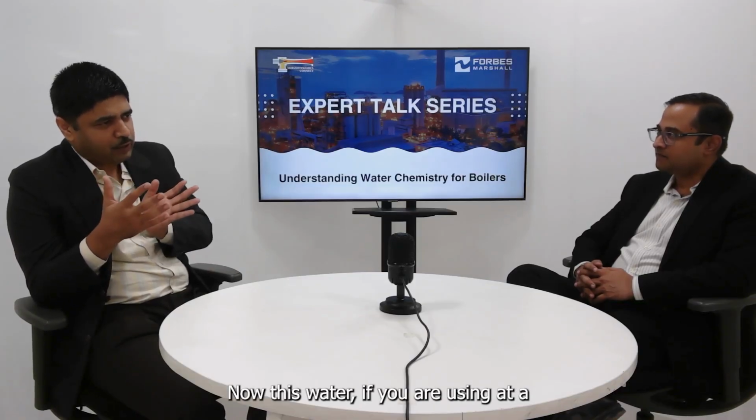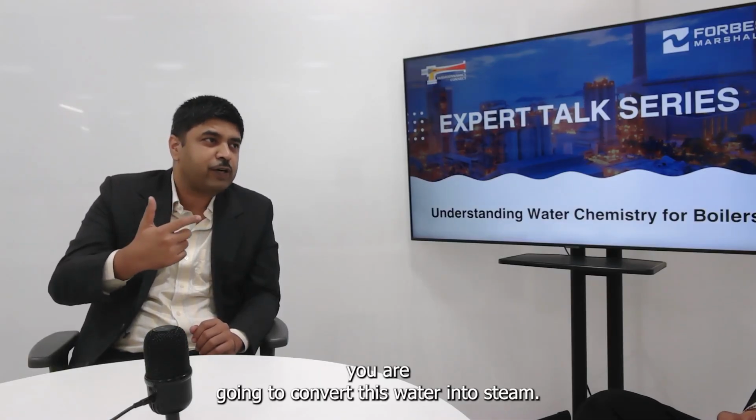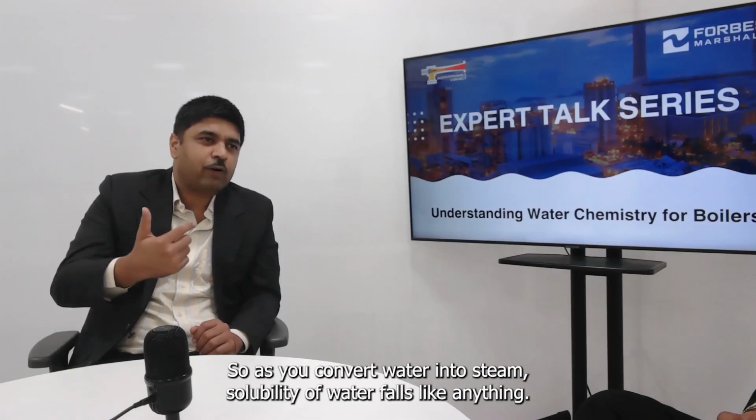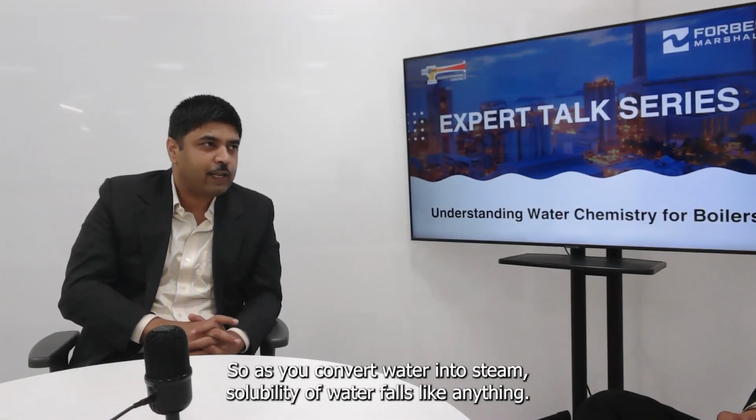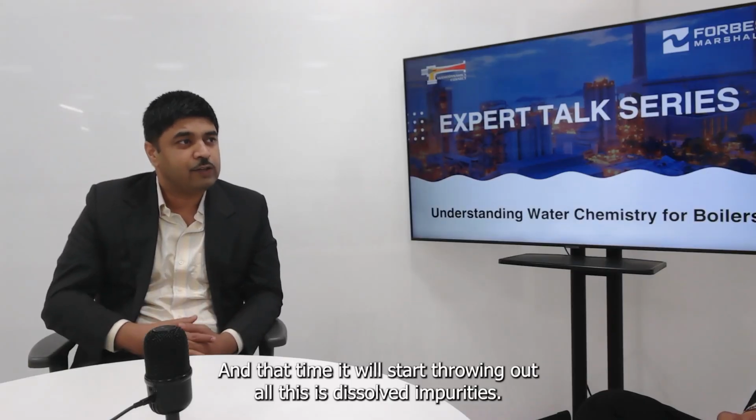Now, if you are using this water for cooling at room temperature with some corrosion inhibitors and some anti-scalants, you can use it as cooling water in normal circuits, like cooling water circuits in your air conditioning, etc. But when it comes to boiler or steam generation, you are going to convert this water into steam. As you convert water into steam, the solubility of water falls like anything. And at that time it will start throwing out all these dissolved impurities.